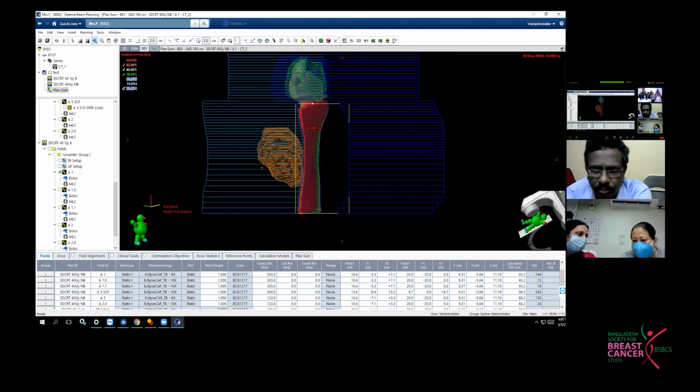But when you use the wizard, sometimes we approve the plan and it has gone for treatment, then it cannot be treatment approved. So we have to think about the MU in that case. But the issue is, if it is a FIF along with wedges, you have to remove the wedge from the field that is going to be used as a subfield, because otherwise it's not deliverable. So that is one thing which is important to note.